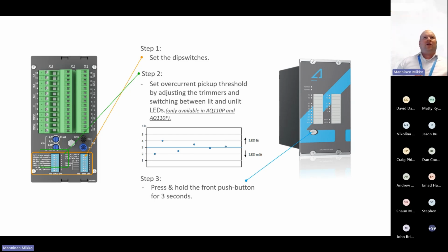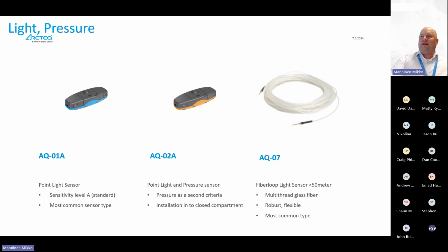Arc flash detection can be made several ways. One way is to use light-only criteria. We just monitor the optical light from the flash and then trip the breaker during the flash. That is done very quickly, in microseconds. Monitoring the current also happens very quickly, typically in less than 1 millisecond, because the current monitoring in practically all of the arc flash protection relays available has been built differently than in typical protection relays. It's not the sampled value, it is something different. But current is one of the criteria.